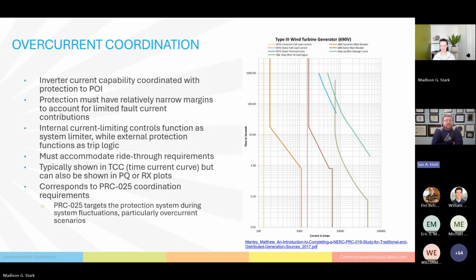Again, just talking high level here while we're waiting for questions to come in, we've been focused very much on PRC 19 as part of this discussion. There are other PRC requirements for generators. Likely if this applies to you, these others would as well. Those, for example, are PRC 24/29. We're moving into 29 now. That's now in effect. PRC 25, PRC 27. As we go forward, we'll very likely have some additional webinars that talk about those PRC requirements in more depth. So just a couple of things to be aware of, especially if you're developing new projects. Some other requirements that may affect you as well are things like MOD 32. Modeling requirements are also part of the same kind of package, and we see those quite often for our renewable projects as well.